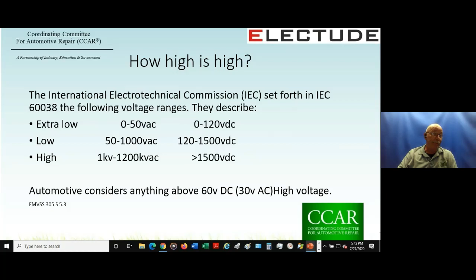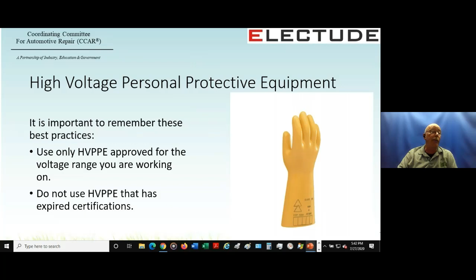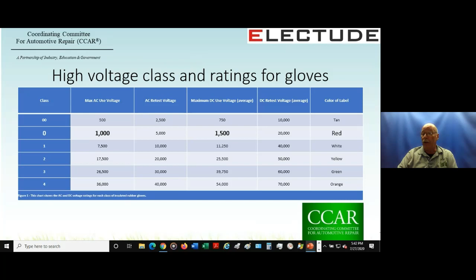All qualified high voltage PPE will have a voltage range and an expiration date. This applies to the rubber products: gloves, boots, sleeves, aprons, all lineman PPE. It's important to use the correct high voltage rating and to have your PPE recertified or replaced once it expires. We are not using any expired PPE. And in our case here, the class for that is class 0, 1000 volts AC, 1500 volts DC, and the color of the tag will always be red.